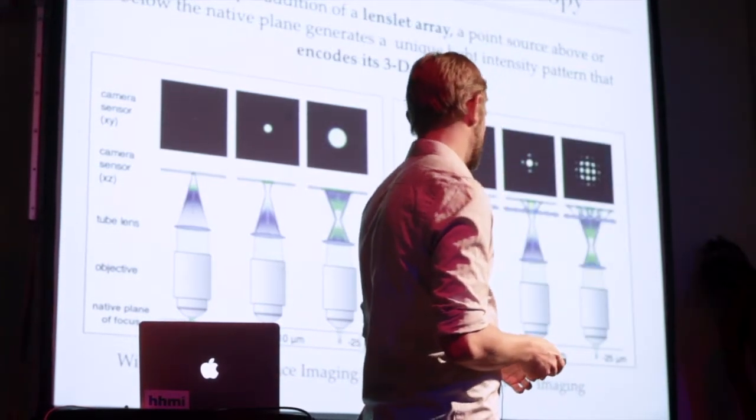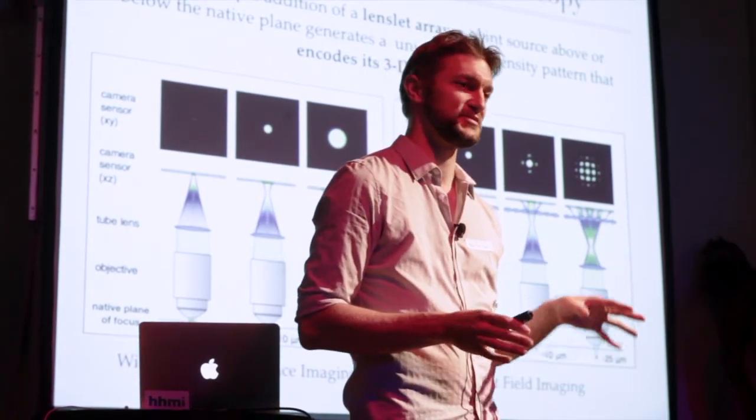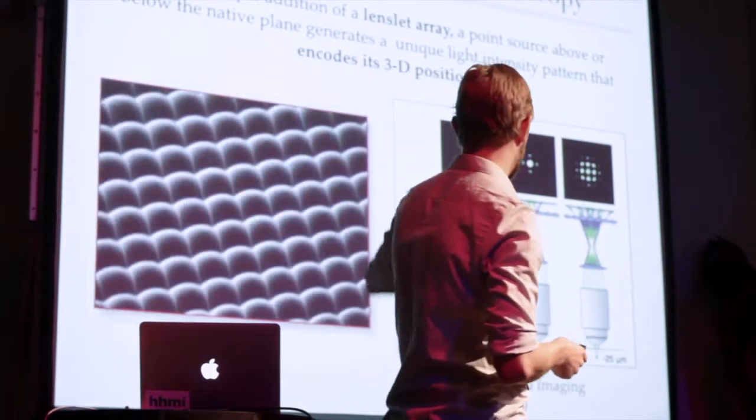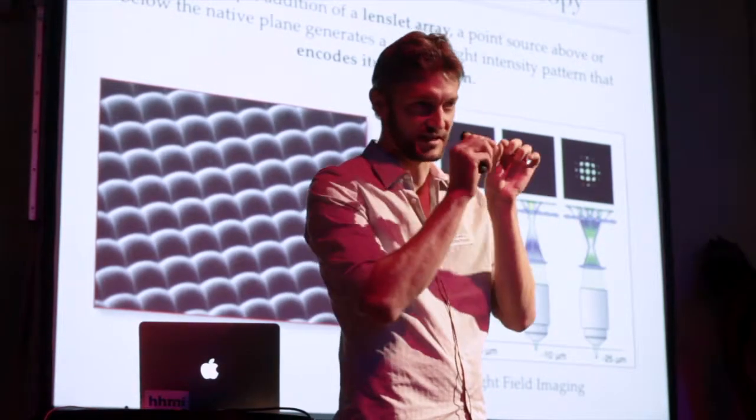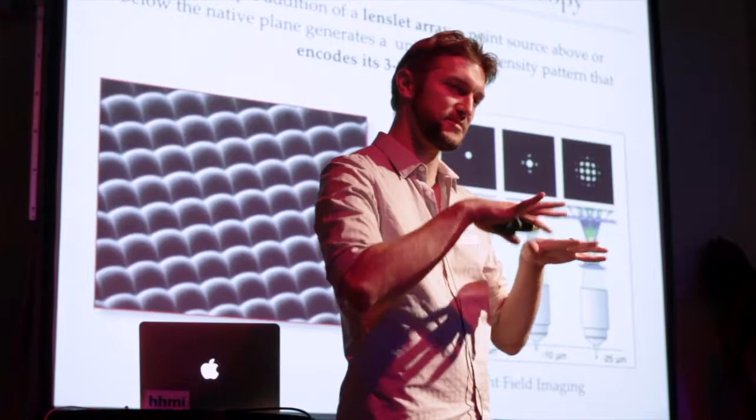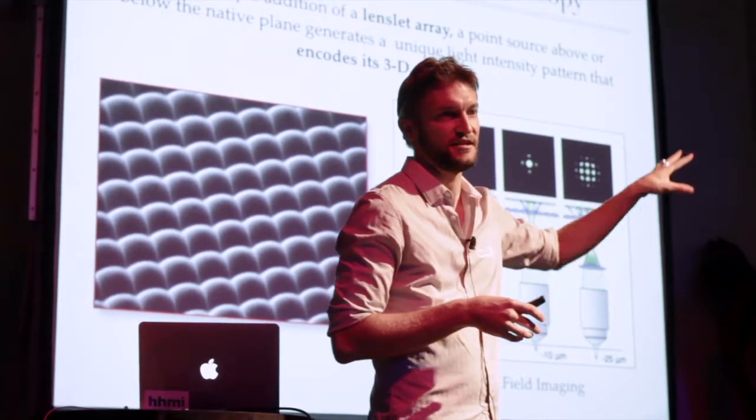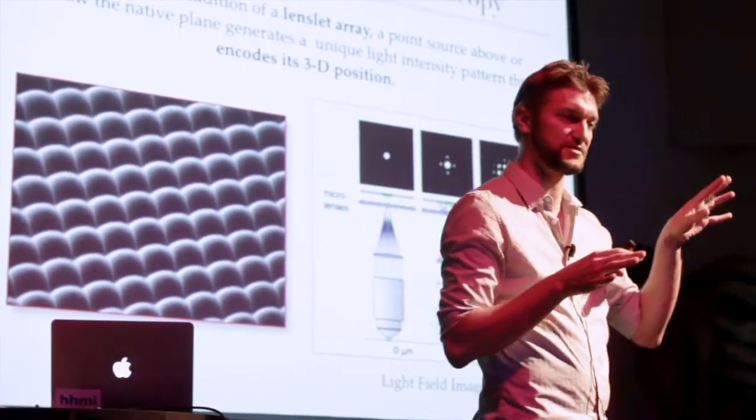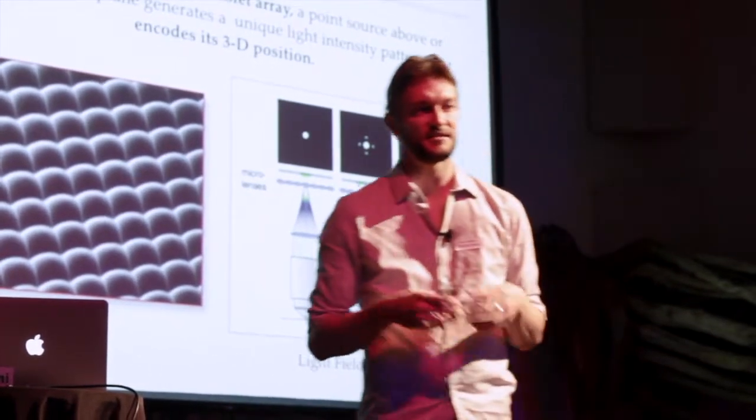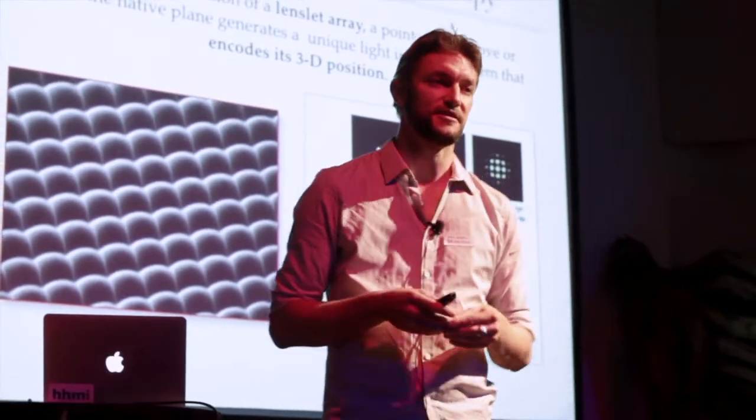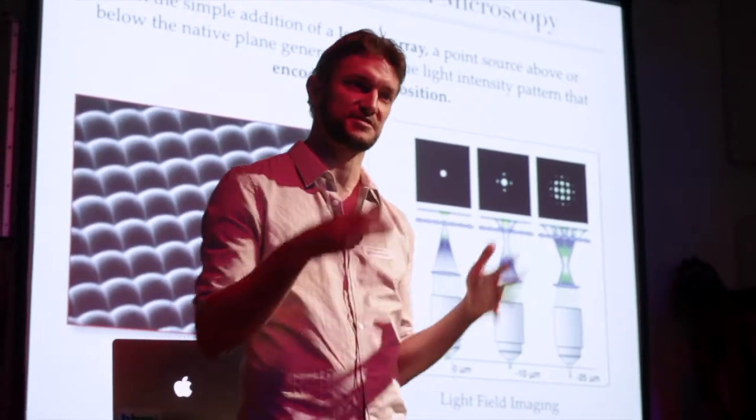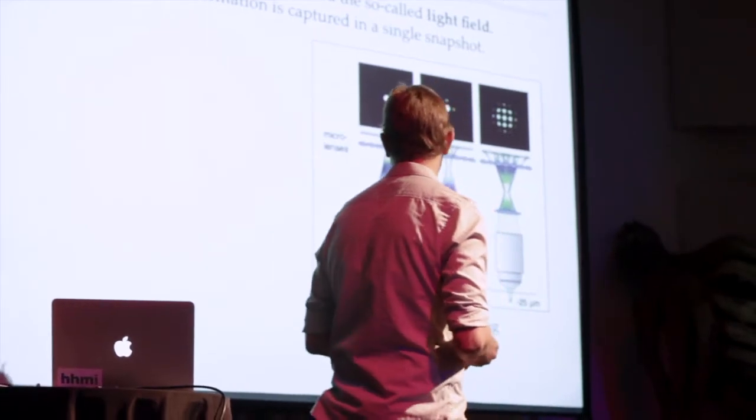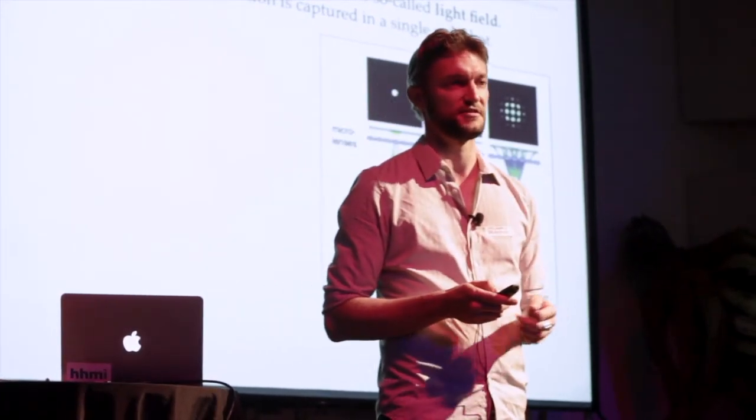So a light-field microscope is actually a very simple modification of a standard fluorescence microscope. You just take the sensor and push it back a little bit and interpose a microlens array. And a microlens array is this little micro-fabricated optic, which has a bunch of these tiny little lenses. And these lenses kind of redirect the light into this interesting pattern on the sensor. And the way that this works, in essence, is that every position in the three-dimensional volume produces a slightly different but very unique and kind of distinctive pattern on the sensor. And it sort of encodes the position of that point on the sensor in a way that allows us to computationally reconstruct where that point was with fairly high accuracy.